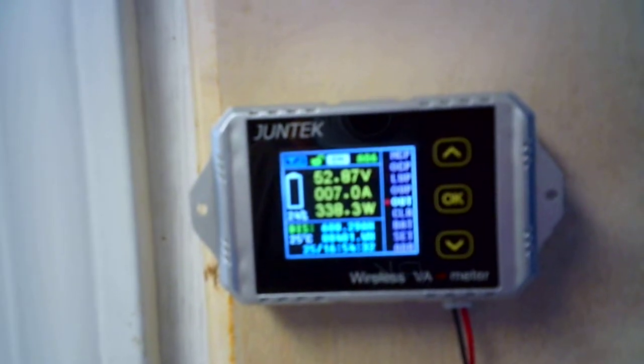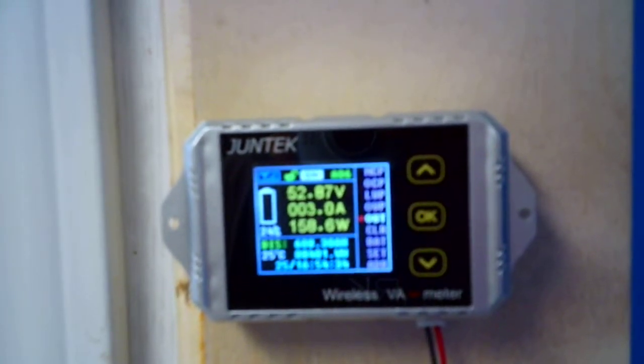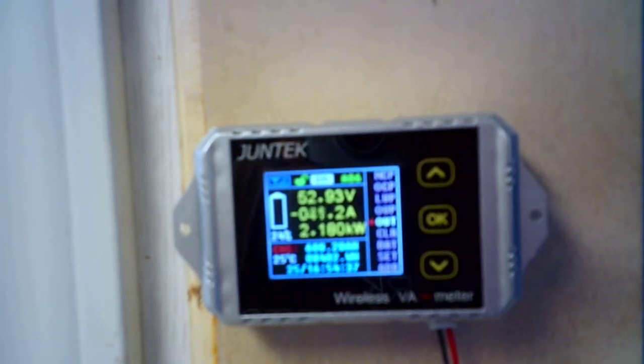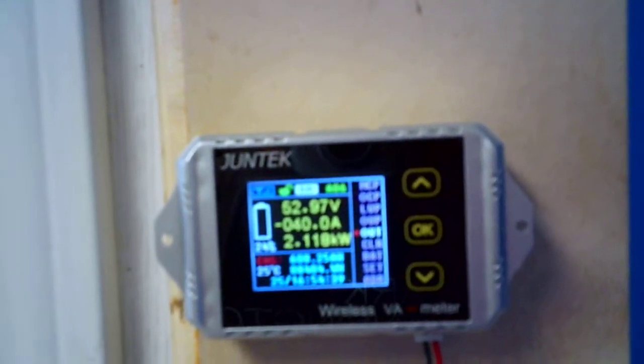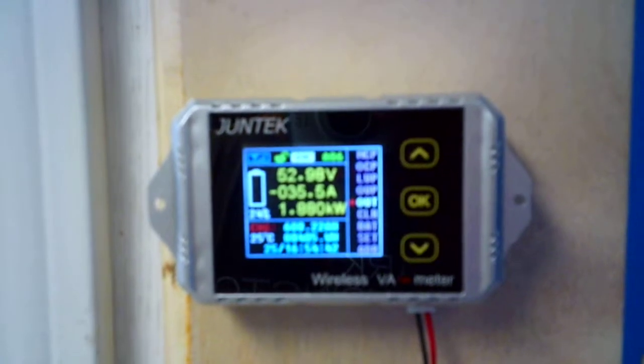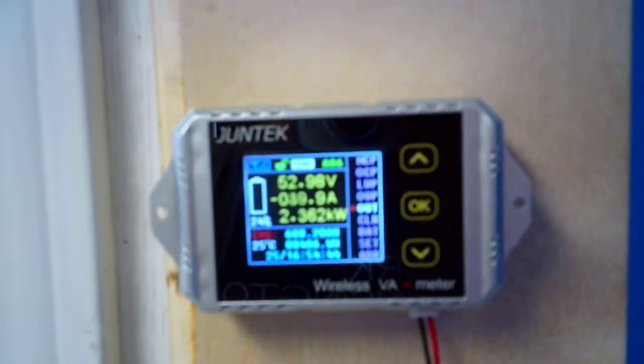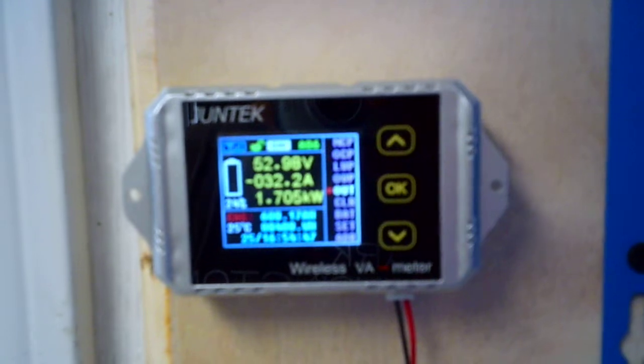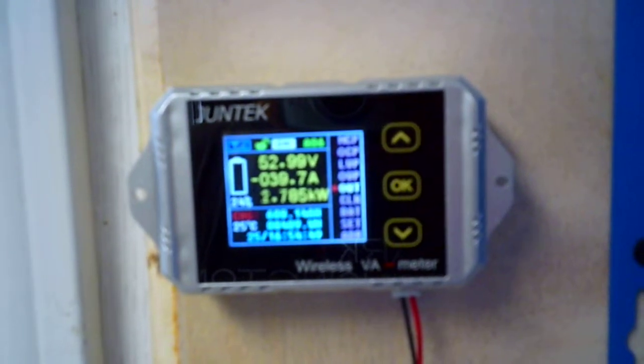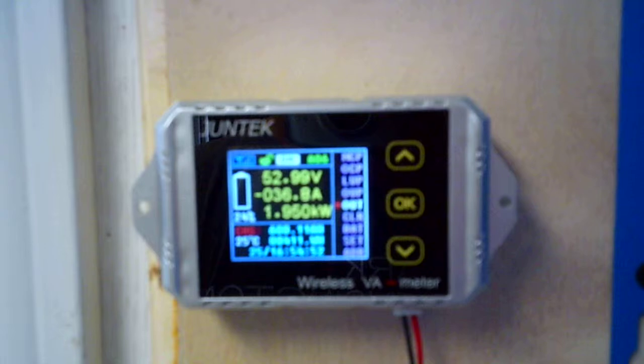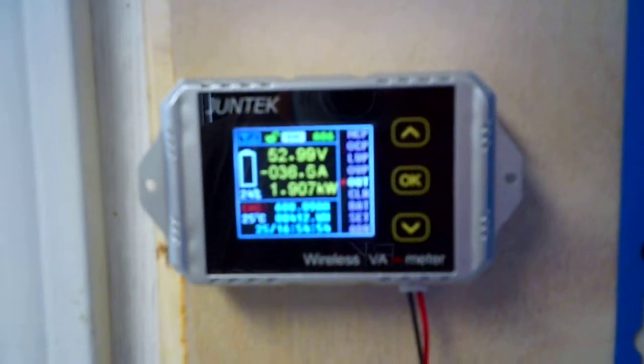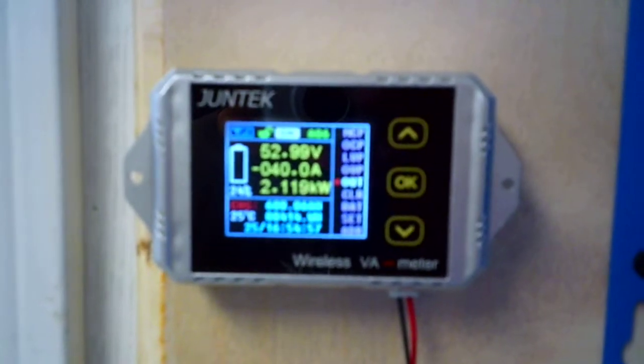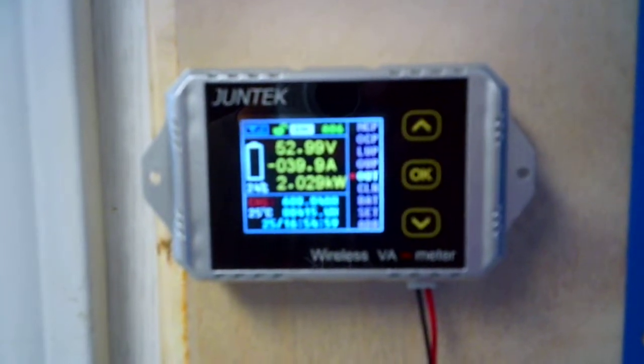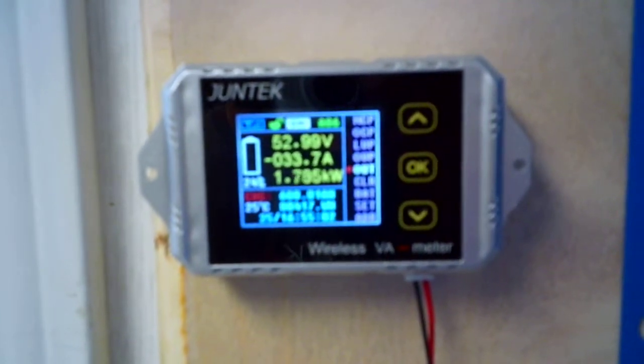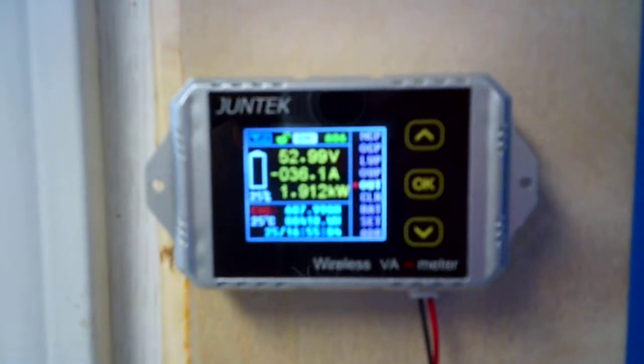That's because the well pump is on right now. You're going to see the well pump kick off here in a second. Then the third readout went up to negative, meaning the solar panels are putting out more energy than the house or garage is consuming, by about 35 to 40 amps. That's what's charging into the battery right now. Down below you can see about two or so kilowatts coming in from the solar panels, and underneath that a little red indicator that says charge.